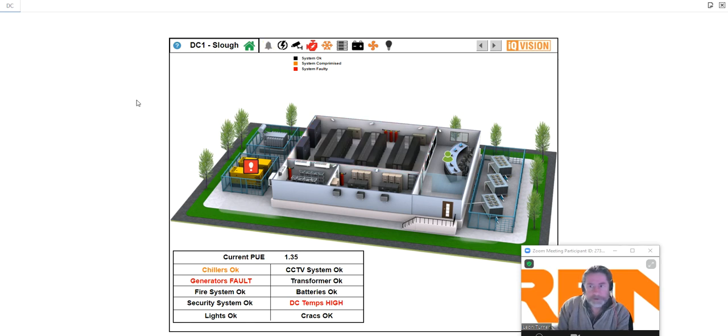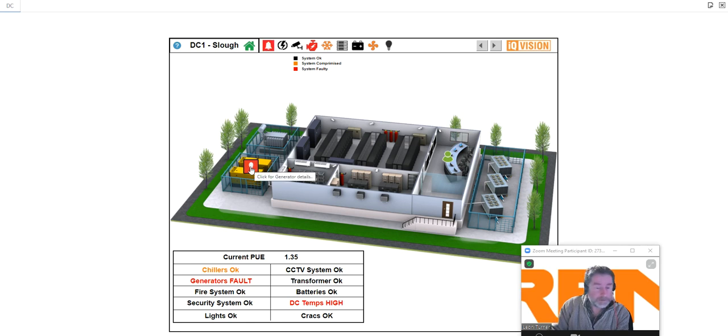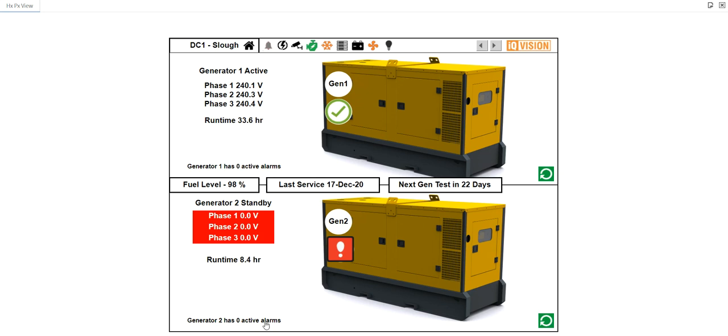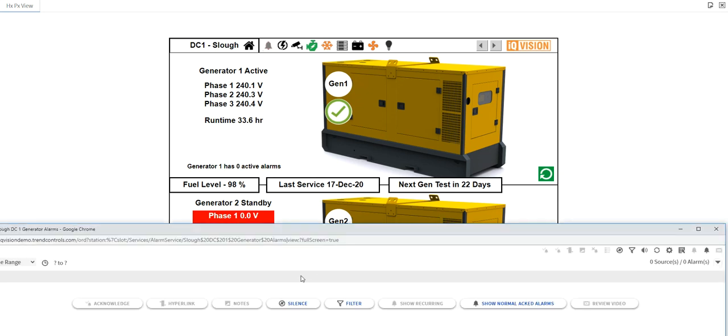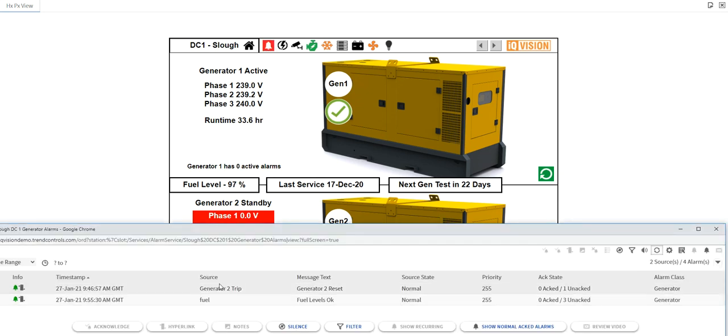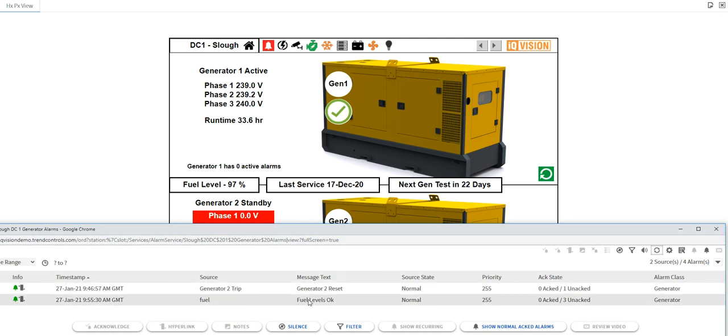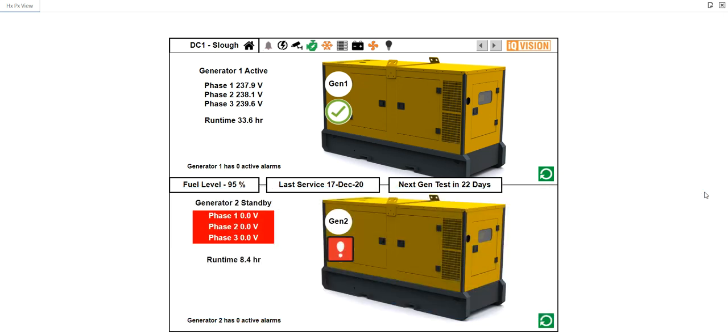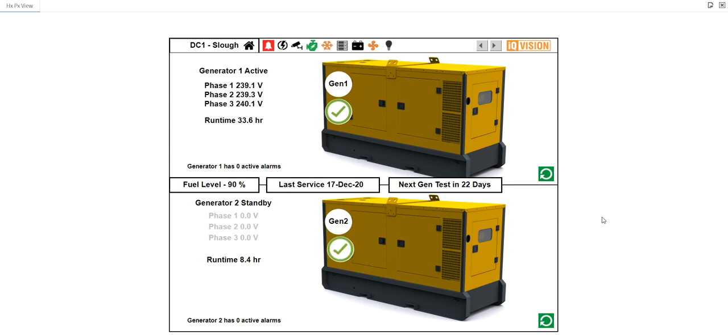If I dive straight in, you can see that one of my generators or something happens to be wrong with some of the generators. If I click on that button, it will take me into the generator screen. It's very obvious one of them is performing better than the other one. I've put in a little reset. It says it has zero active alarms, which is interesting, but we can probably go and see. It says generator trip. There's also a fuel level warning, but that's not necessarily a job for right now to worry about. If I hit the button, we can try and force a reset.